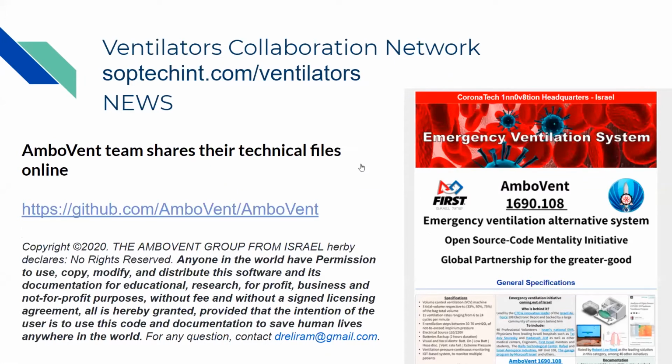We are a team made of about 40 people that came together on March 18th. There was a call out from our health department that they want to develop a BVM-based ventilator, which we translated immediately as a last resort ventilator, because in the medical aspect, BVM ventilators are not meant to be used as a long-term ventilator for patients because it's a volume-based ventilator.